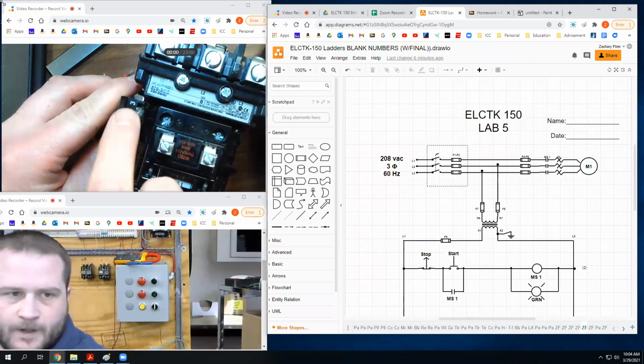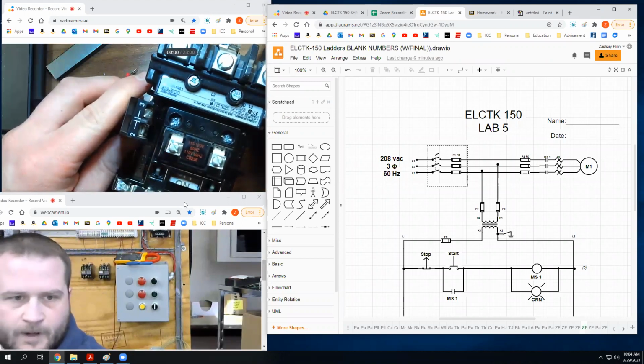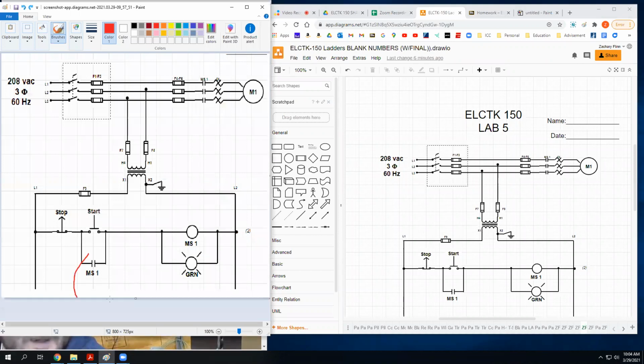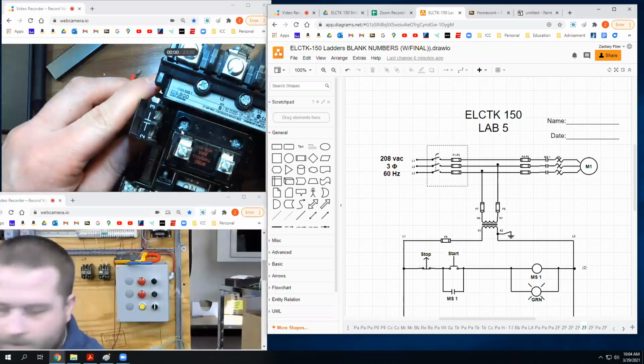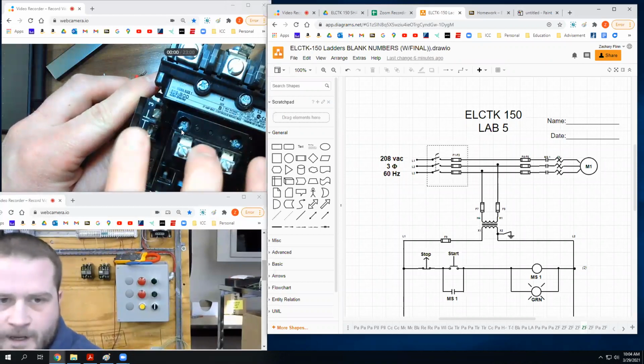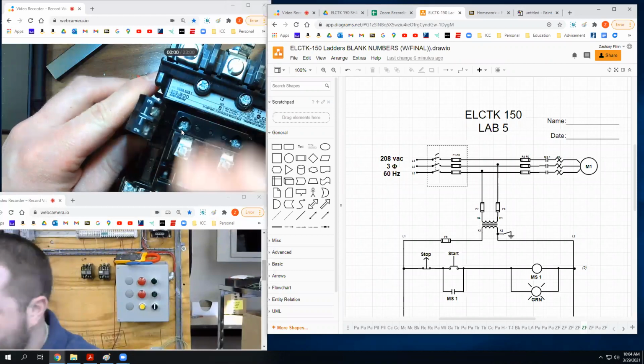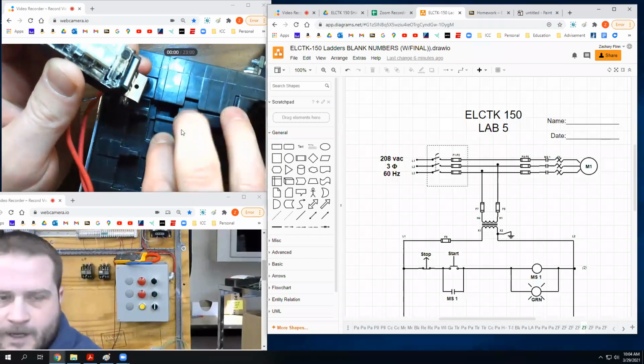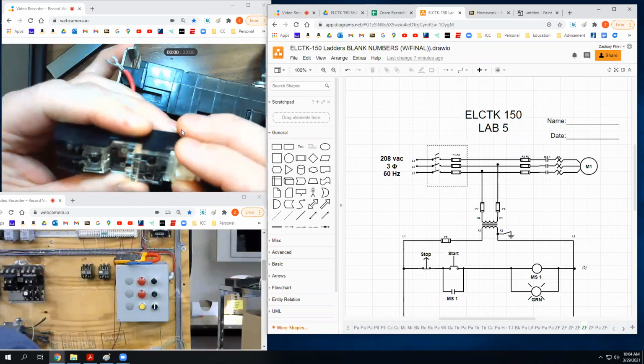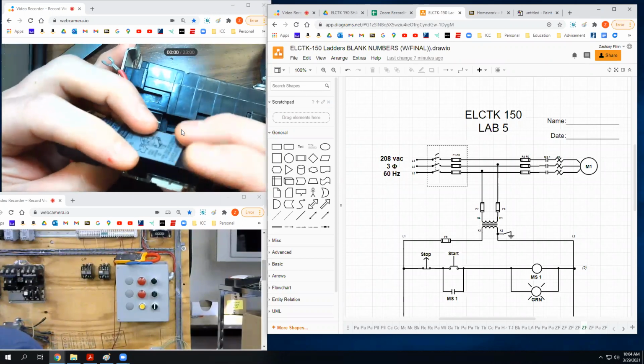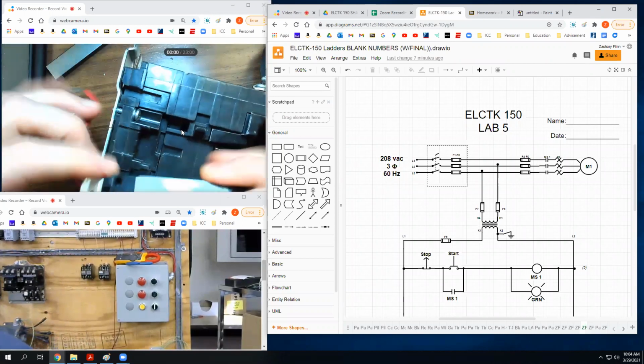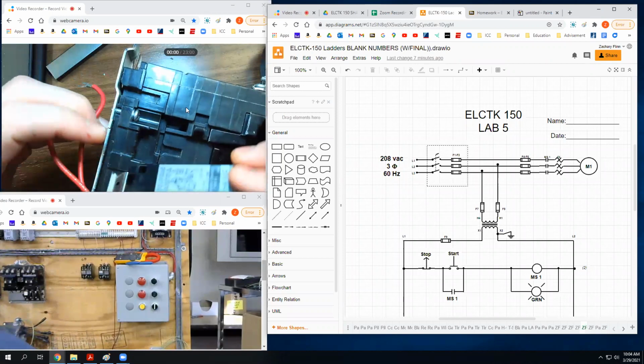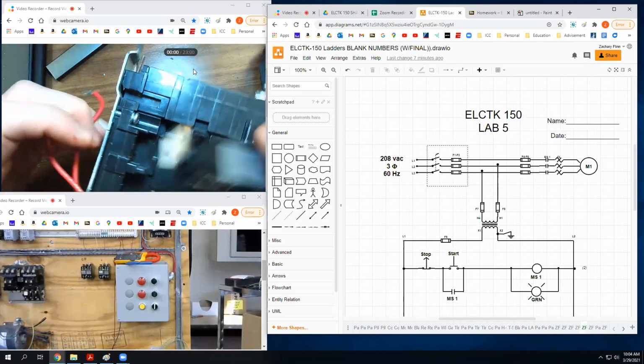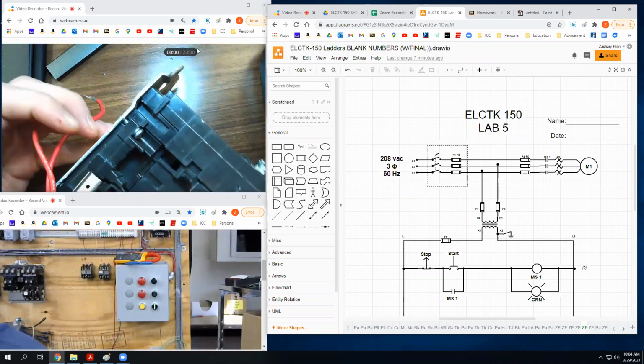You see how it's a normally open contact? That is, on your print, this guy. It's called an auxiliary contact, and we're going to use this to maintain this current going through here once I push the start button. How it works is on the back side, this little notch fits into this spot here. Okay, it's mechanical. It mechanically moves this. And inside here, it's going to be hard to see without taking this apart, but you're welcome to look at one of these de-energized. Basically, when this gets clicked in there, I don't remember how that clicks in.